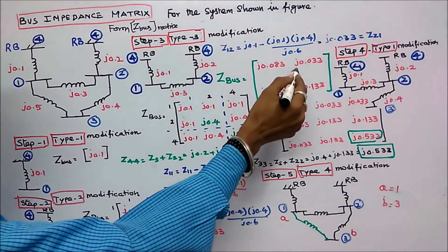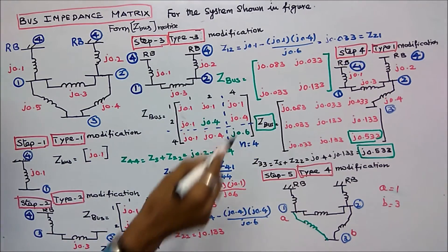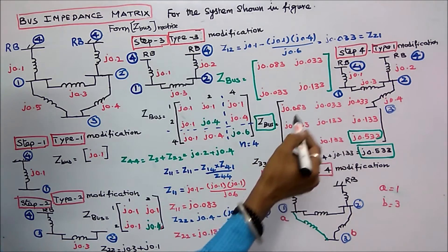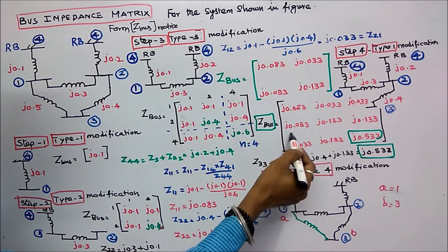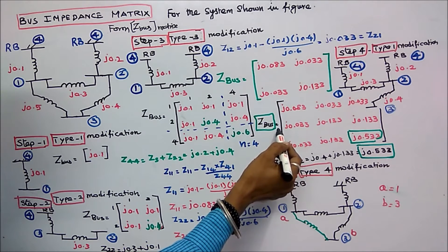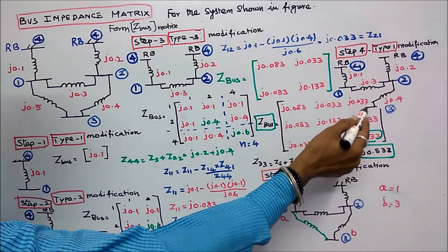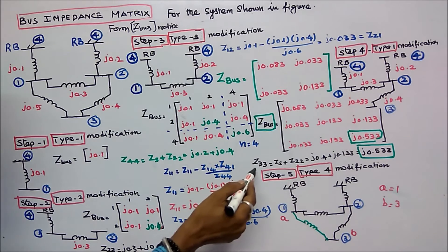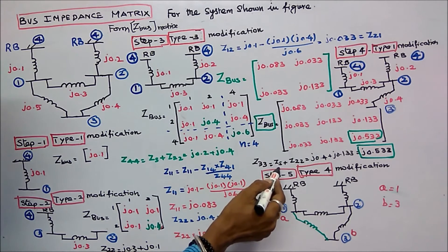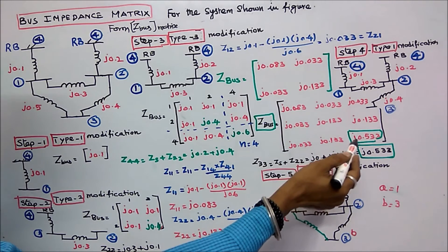Step four is a type one modification. I am connecting new bus three to the old bus two. Now I got a three by three matrix. The matrix values are: Z11=j0.083, Z12=j0.033, Z21=j0.033, Z22=j0.133. Z33 equals Zs plus Z22; Zs equals j0.4, Z22 equals j0.133, therefore Z33 equals j0.533.